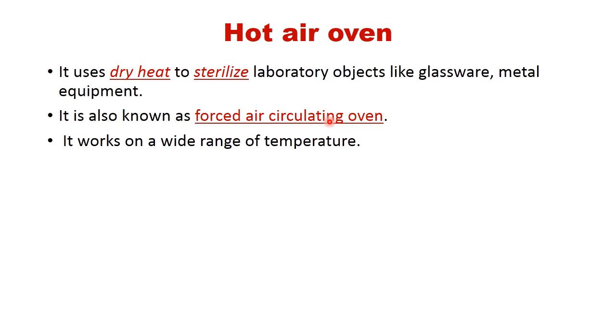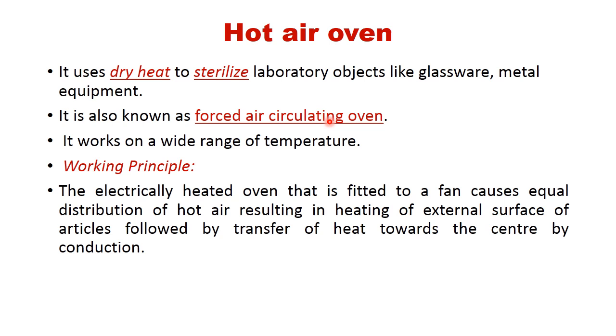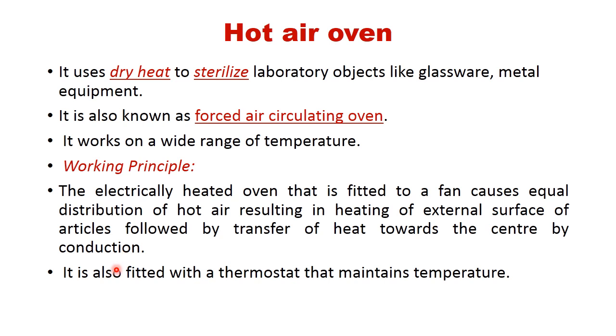It works on a wide range of temperature, and the span of temperature may be 50 to 200 degree centigrade. The working principle of hot air oven: the electrically heated oven that is fitted to a fan causes equal distribution of hot air, resulting in heating of the external surface of articles followed by transfer of that heat towards the center by conduction. So, it utilizes dry heat that is conducted from the external surface to the center of the objects that need to be sterilized. This hot air oven is also fitted with a thermostat that maintains the temperature.